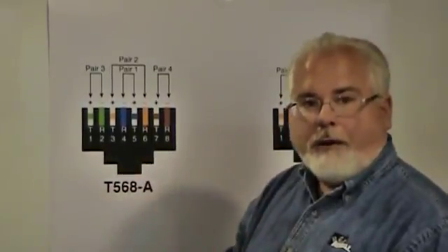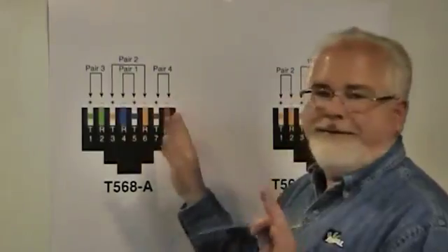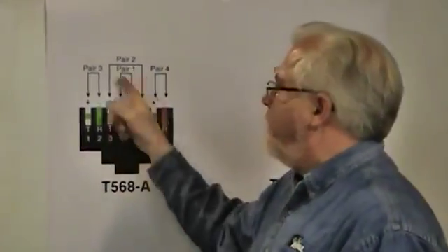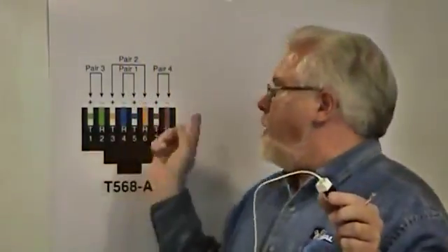And when you look at 568A compared to old telephone wiring, and remember USOC, how that was wired, and again, check out the wire color code configurations for phone circuits, you'll find that pairs 1 and 2 are in the exact same spots as they are in traditional phone jacks, okay? And that's how come this Cat5 jack can be used for phone. So if I want to have a phone come into the outlet, I'll go to the other end and plug it into the phone board and apply phones across pins 4 and 5 here. And now a customer at the outlet in the room can take his RJ11 4-conductor phone plug and snap it into this 8-wire jack, and it hits the 4 metal pins here, which is all I needed it to do. And I can use it for phone.